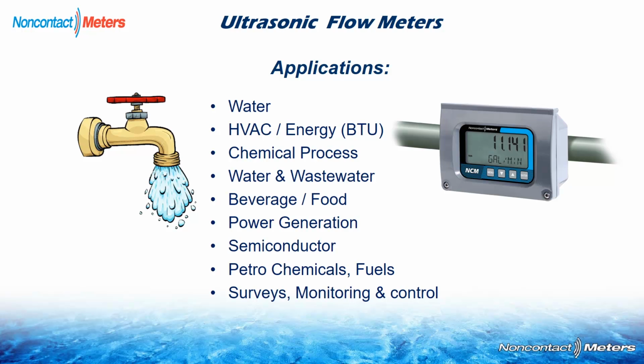The basic operation of an ultrasonic transit time flow meter is ultra pure liquids up to about 2% suspended solids. An example would be, say, DI water, sewage, but not sludge or oatmeal. Needless to say, water and wastewater are very popular applications, as are beverages, power generation, and the list goes on and on. Depending on your application, you may need to use either a portable or a dedicated ultrasonic flow meter.